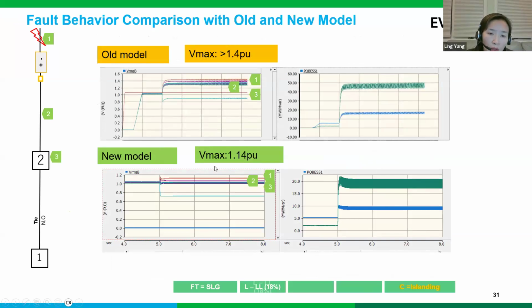As I mentioned before, in the early stage we also identified transient overvoltage and high voltage under single line to ground faults. In the last scenarios in the previous models, we identified that the maximum system voltage would be above 1.4 per unit, which is not acceptable. With the new model, we were also able to define and set the fault outputs with different parameters, and with those updates under the new model, we are able to adjust the fault contribution of the inverter.